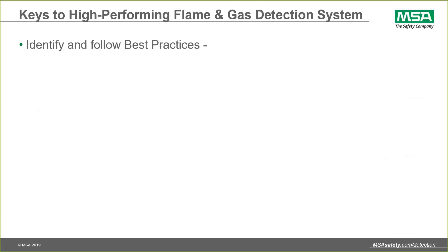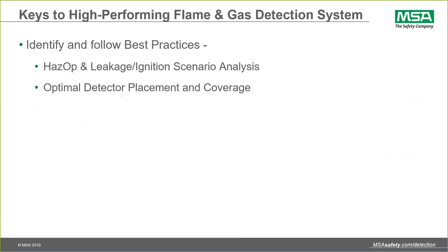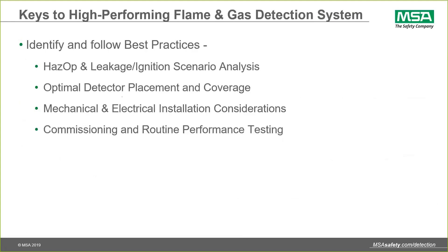Best practices for achieving a high-performing system include executing a HAZOP and ignition scenario analysis — identifying what events are most likely to lead to a fire ignition on site. Once that's done, we can consider the effectiveness of different detector placement options and coverage angles. Proper mechanical and electrical installation considerations are required: a solid mounting structure, compliant electrical installation with conduit or cabling, and power distribution. Once we have a fault-free system, we commission it and establish routine performance testing, well-defined operation and maintenance practices, a logbook, physical inspections, and training for operators and maintenance personnel.